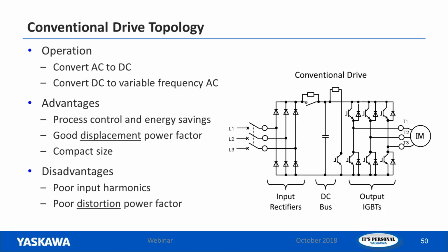Don't be intimidated by this slide. I just want to cover some conventional drive topology to broaden the understanding of how this all works. What an AC drive does is it converts AC to DC, and it does that through this input rectifier here. So we've got a diode module where we take our 3 phases of input power and we rectify it into DC. So if you've got, say, 480 volts on your line, it's going to get rectified to DC. So our DC bus now is going to be sitting here around maybe 660, 670 volts DC. And then remember, as I mentioned earlier, the line voltage in America is 60 hertz. So it's only one speed then for an AC motor. And we need a way to change the frequency.